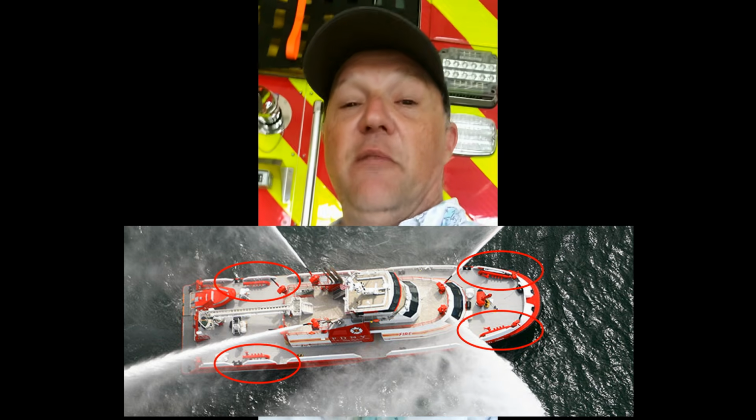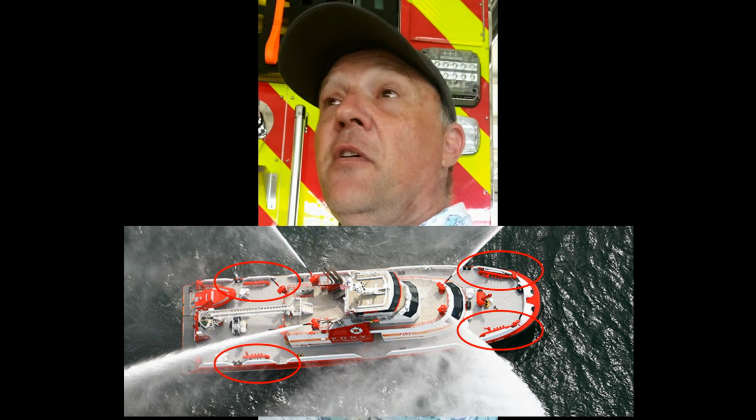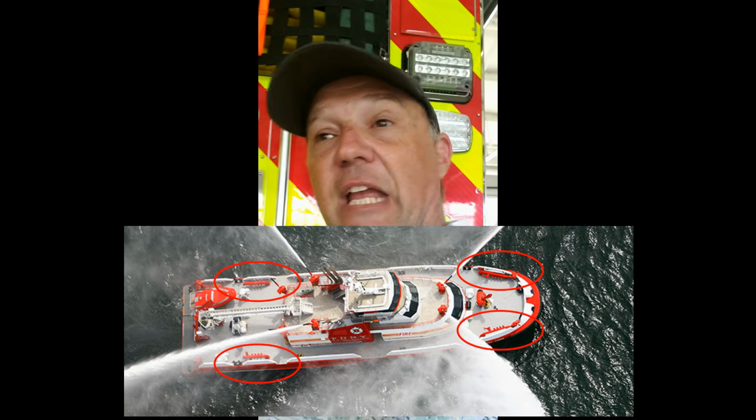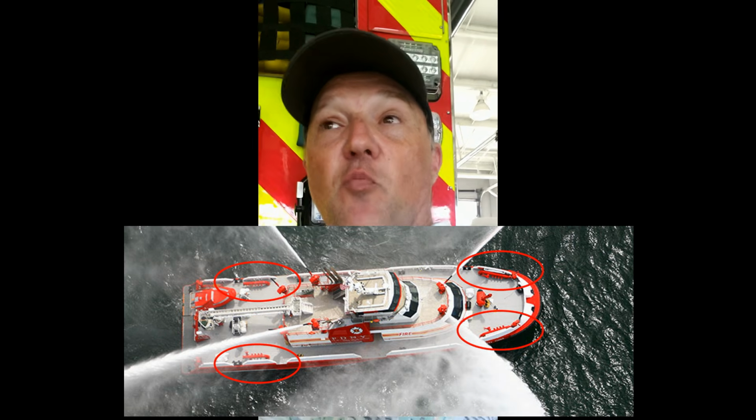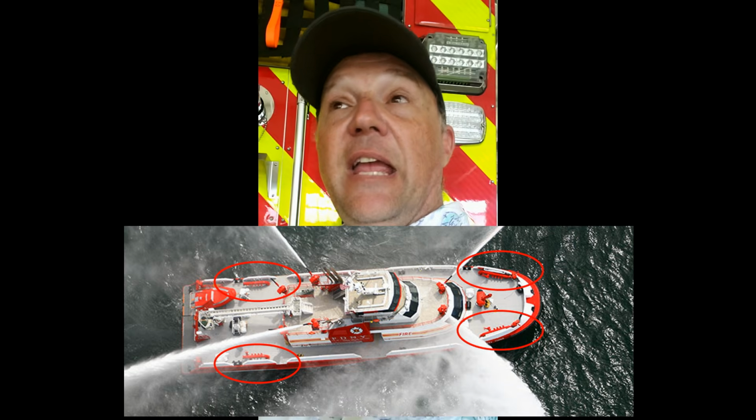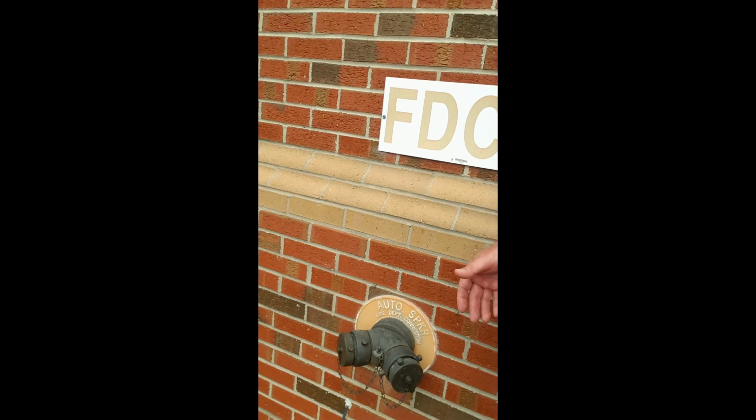And what makes those fireboats really important is not spraying water like you always see, but they have manifolds, they have hookups along each quarter of the vessel, the 2 up front, 2 in the back part of the vessel. And you can hook your engines into it, and what you would then do is be able to pump into the vessel. So on many buildings and structures you'll see what are called FDC. These are fire department connections. And this is where you hook in your fire truck to a building to supplement the interior either sprinkler system or the standpipe system. Those are those pipes that you'll see within stairwells, so that if you have a fire in a structure, you can bring your hoses with you, climb the stairwell, hook into that, and you're fighting through the piping system that's there.